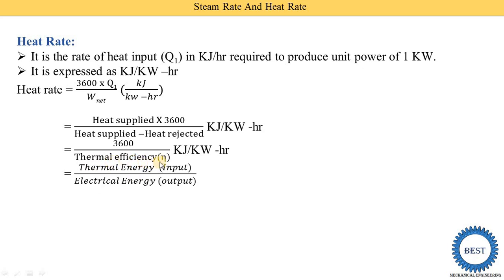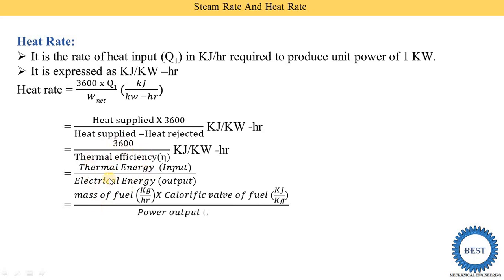Thermal efficiency is equal to output divided by input — electrical energy produced is the output and thermal energy is the input. Thermal energy is produced by burning fuel — that is, burning some mass of fuel in kilogram per hour. For example, if we burn 500 kg of fuel in one hour, and the calorific value is 40,000 kilojoule per kg, then by burning 1 kg of fuel we can produce 40,000 kilojoule of energy — this is called the calorific value.